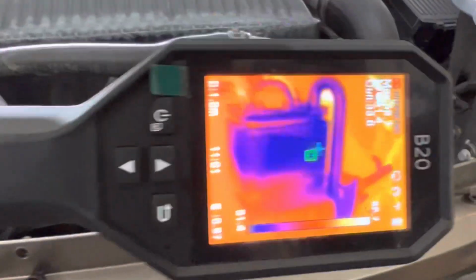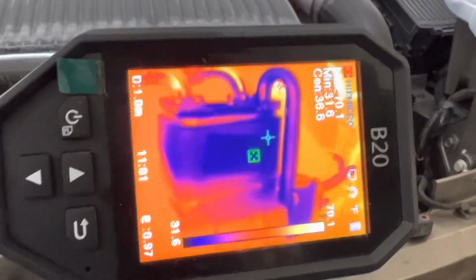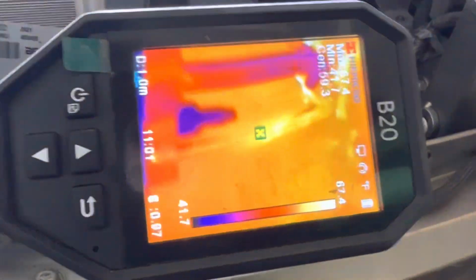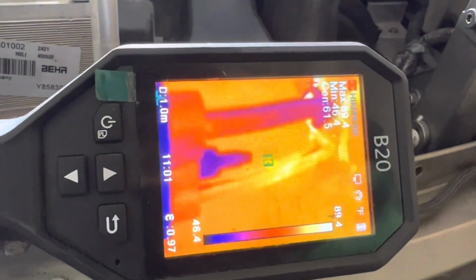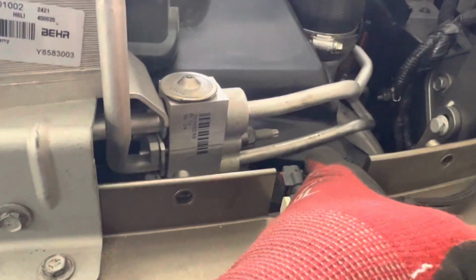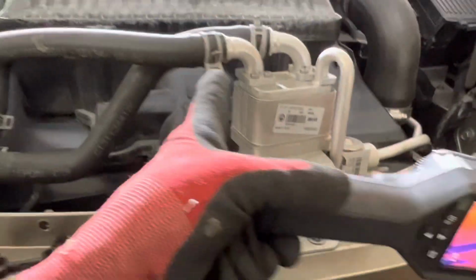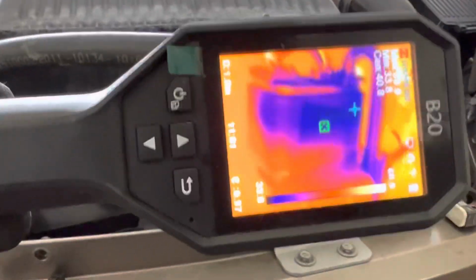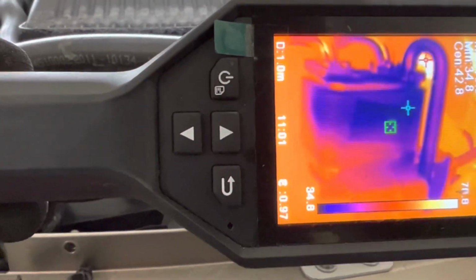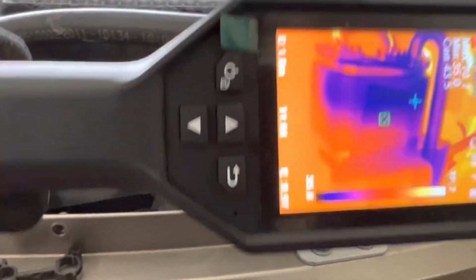Let's take a closer look here. You can see the cold refrigerant, and if you look down here you can see the hot refrigerant and the cold refrigerant. So there's our hot liquid, there's our cold. There's our expansion valve going into the plate heat exchanger that has the glycol going through it. You can see where it's entering, and it's colder on top, or entering—let me get the temperatures correct here.